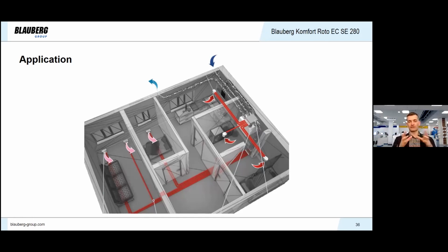So gases from the kitchen hood are extracted by the unit and then evacuated outdoors. In this case we also show the Blaufast semi-rigid duct system connected to the unit, but the supply distribution box is installed on the floor, and supply ducts are installed in the construction of the floor. This is one of the most efficient ways to ventilate a house or apartment, when the supply air comes from the floor grills. On the other hand, extract grills are located at the ceilings of the dirty premises like kitchen, utility room and bathroom. This is a standard and efficient solution, so we can recommend using it like that in all your projects.